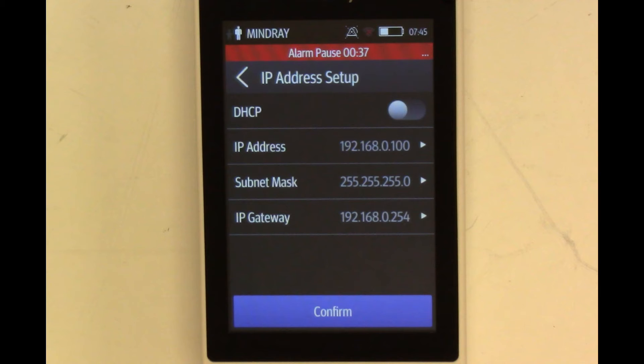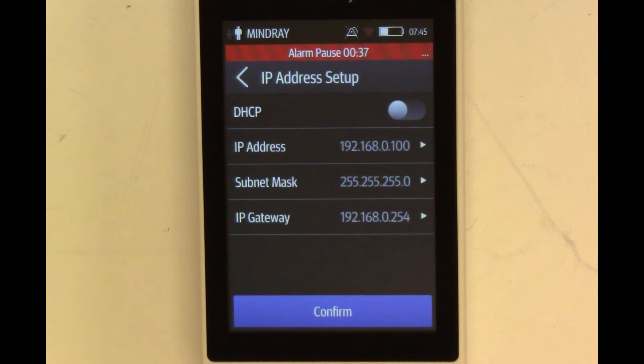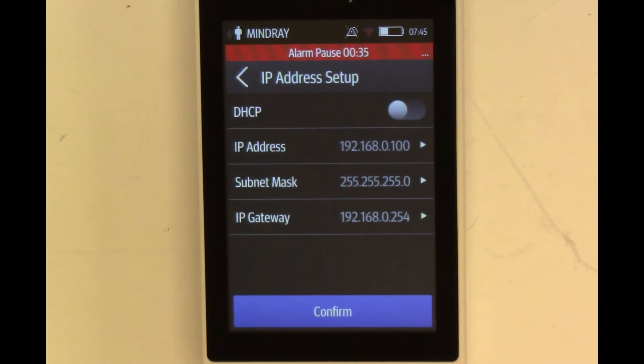You will enter the same IP address from the TM80 that this TM80B is replacing. Change your subnet mask and default gateway to match the other TM80. Select Confirm once you know your network settings are correct.